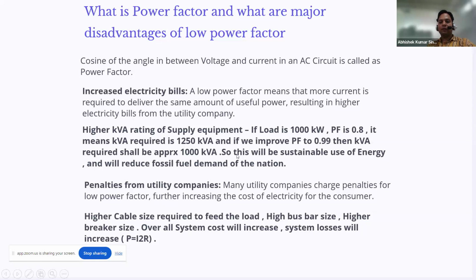If we improve the power factor, this will be a sustainable use of energy and will reduce the fossil fuel demand of the nation. As we all know, fossil fuel is getting depleted very fast, so we have to take care of this. Even though the government is saying that you have to maintain 0.9 or 0.95, you should maintain 0.99. Always maintain 0.99, either by placing active filters or a hybrid panel, whatever is the best solution for your plant, your industry. You have to maintain a 0.99 power factor, which is very important. In case you do not maintain it, the government is going to plan penalties on you. Right now, if the power factor is less than 0.9 or 0.8, then penalties are imposed, and the government is imposing them.